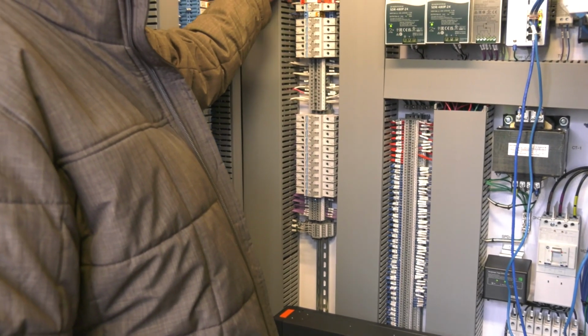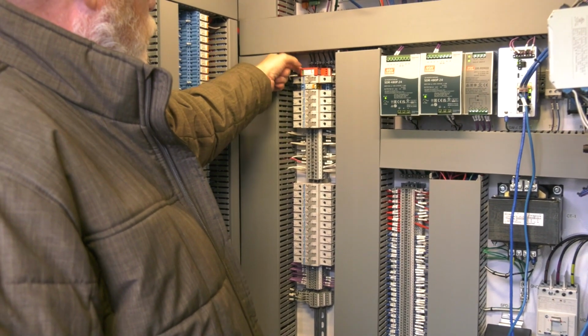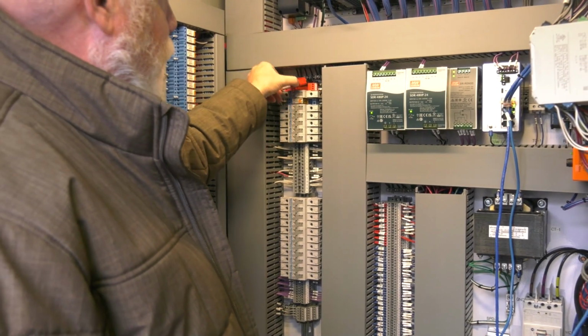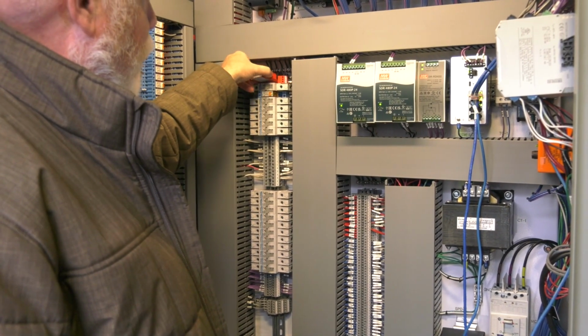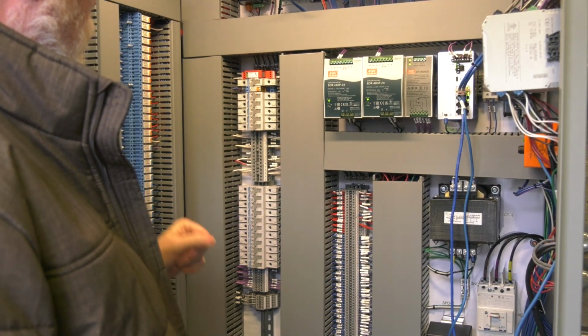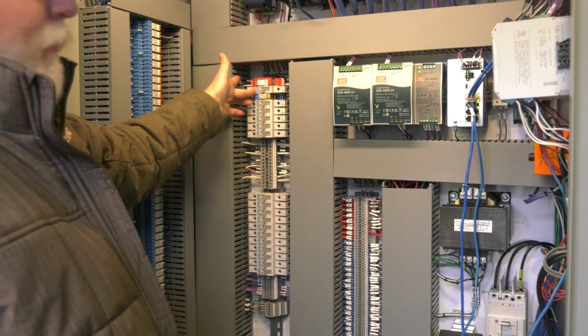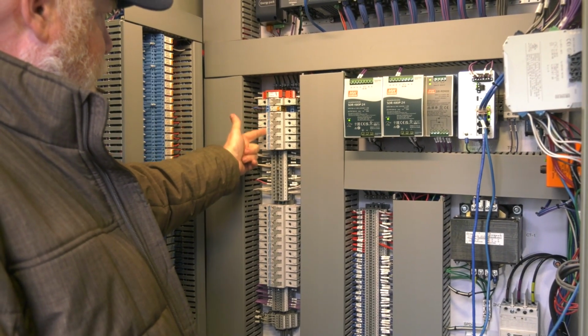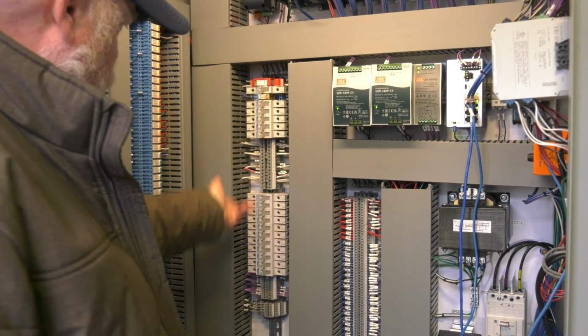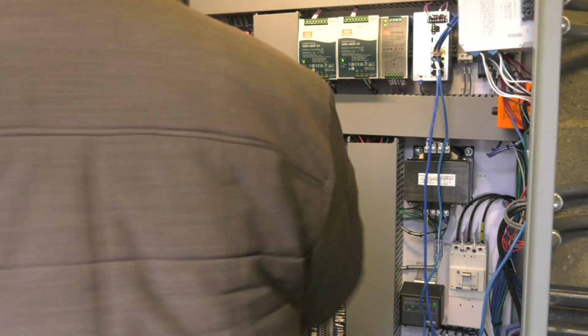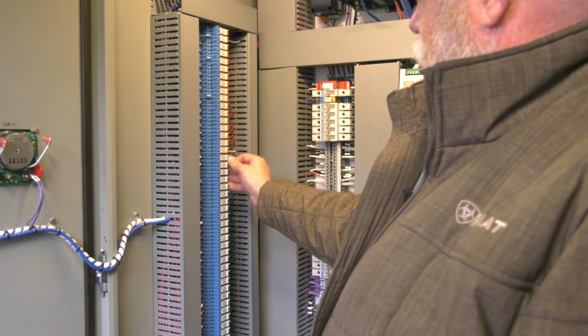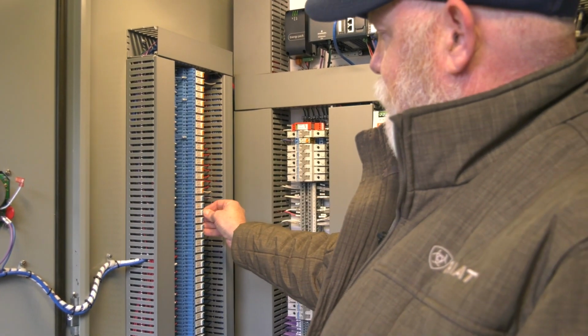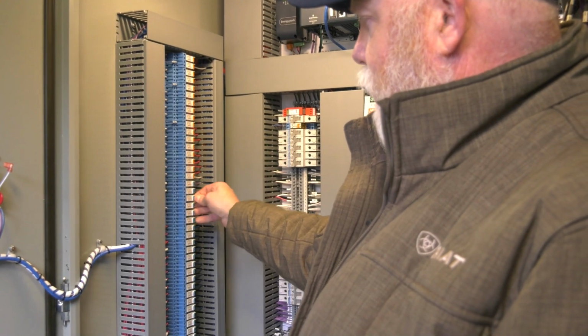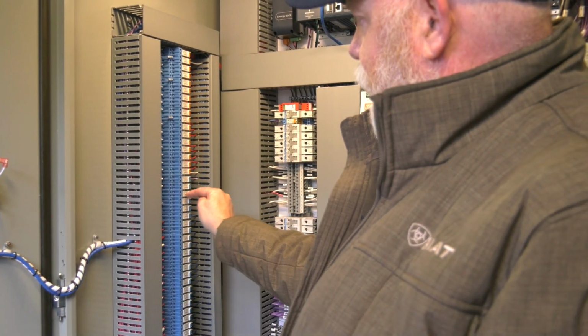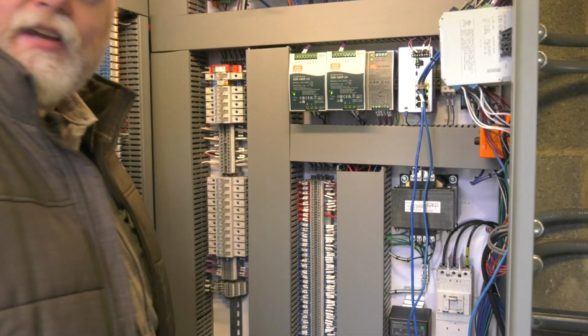Let's see. We've got a 120 volt surge suppressor, which is make before break. So if the module goes bad, just remove it and you'll stay up. This is the main circuit breaker. Let's see, breakers, relays. Your relays right here, you got buttons. You can push your button in, and it's the same as being energized. You can break the little tab off, turn the flag, and it will force that relay on. And I believe that's it.